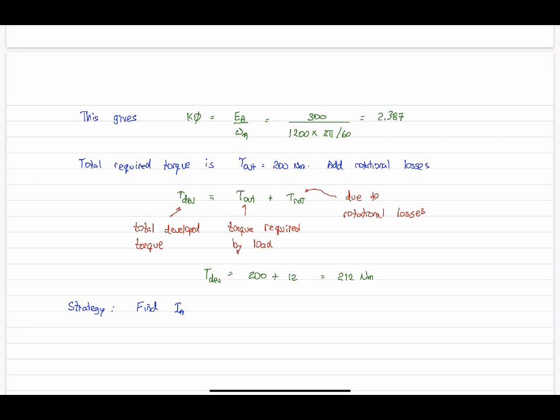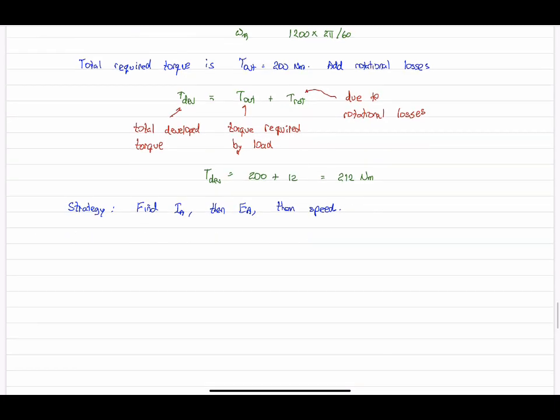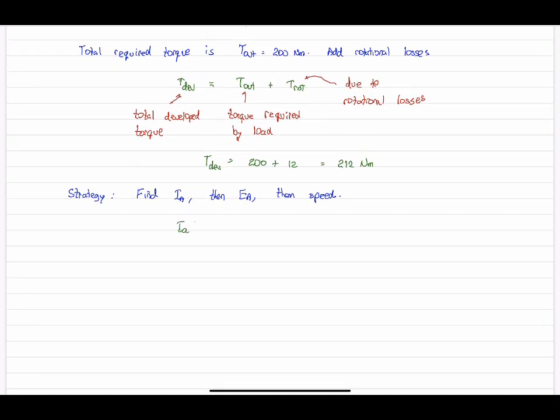So why don't we find IA first? We already know what the developed torque is, 212 newton meters, and we know the machine constant. So let's use the numbers we have. And we end up with 212 newton meters divided by the machine constant, 88.8 amps of current.